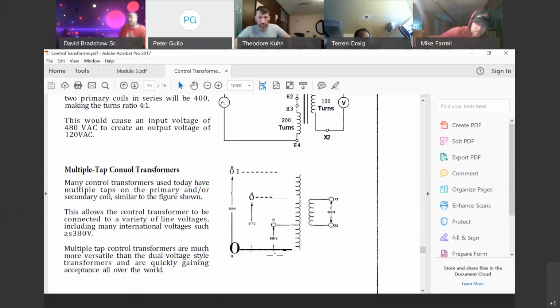We're just concerned about 208 input on the primary. We don't care about 277 volts, we don't care about 380 volts on the primary side. All we're concerned about is pin 2 and pin 3 on the primary side. We're gonna put 208 volts going in, and coming out of that we're gonna get 120 volts. There's multiple taps on the transformer we have out there at Northland, but we only care about the 208 tap.